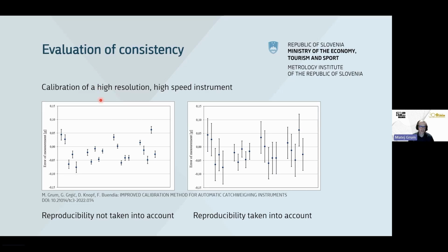The measurements were done on a high resolution instrument. For example, the resolution was lower than 1 gram. It was 0.1 gram, but the capacity of the instrument was about 1 kilogram and more. Not taking reproducibility into account, we got this result: our error of measurements for a certain number of cycles for the same load. The uncertainty is relatively low, but it can be seen that particular measurements are not in good agreement with other measurements of the same load.